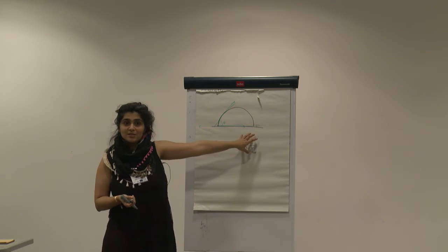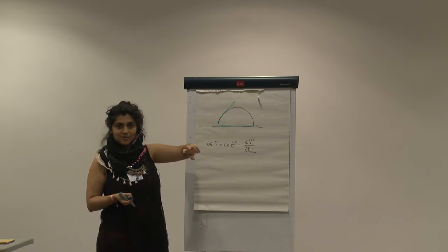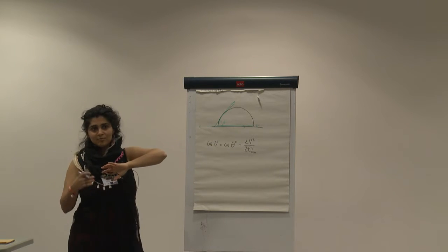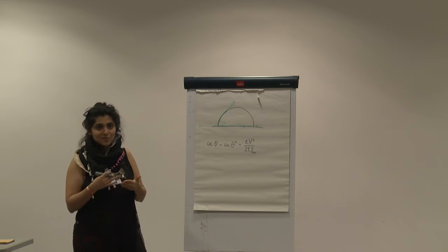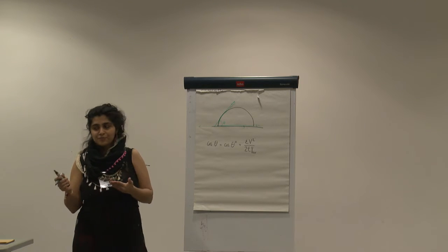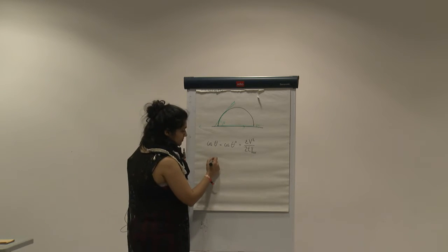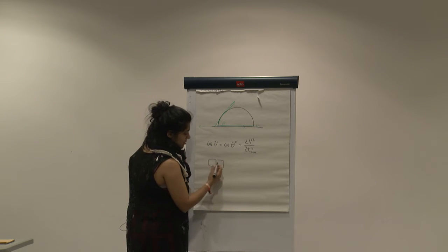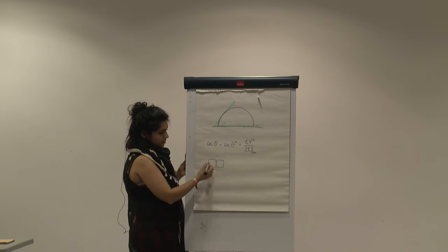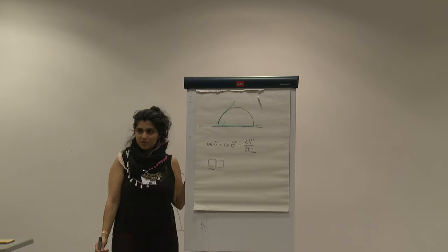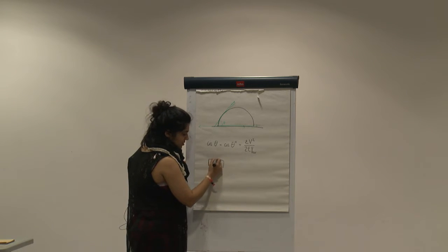However, if we're working with samples like cells, we may be concerned about that. And since we're operating with those devices and we want to have them running for an hour or two, we don't want to have super high voltage because electrons can also jump from one electrode to another. To give you an idea about dimensions, these electrodes are usually 1 to 3 millimeters in size. Electrode pitch is what it's called.